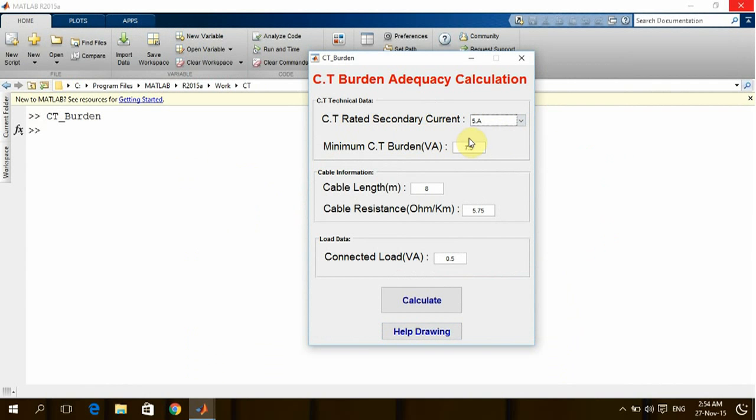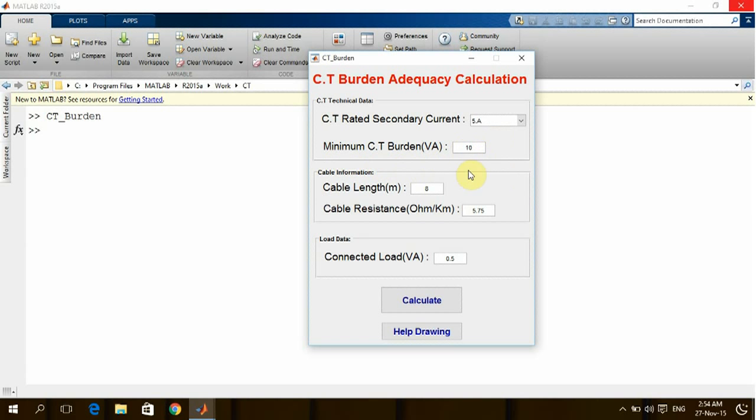If I want to use a CT with secondary output of five amps, this is the maximum burden of CT in volt ampere. We can take it from the manufacturer, so let's consider the CT can give me maximum 10 volt ampere.